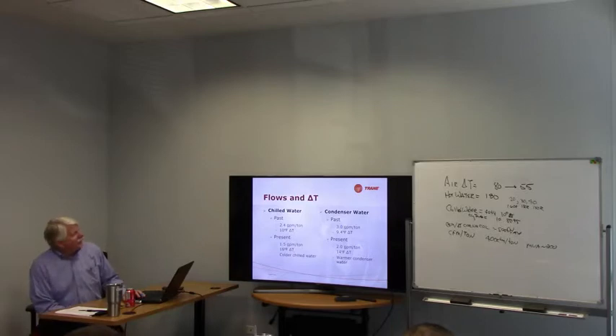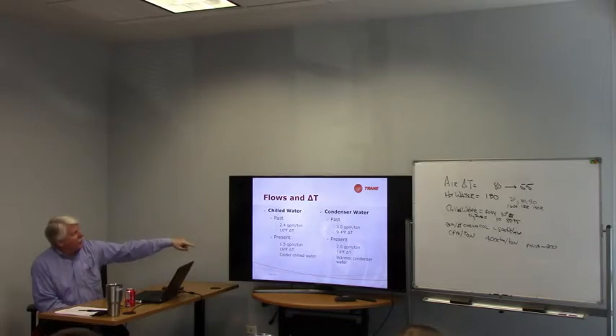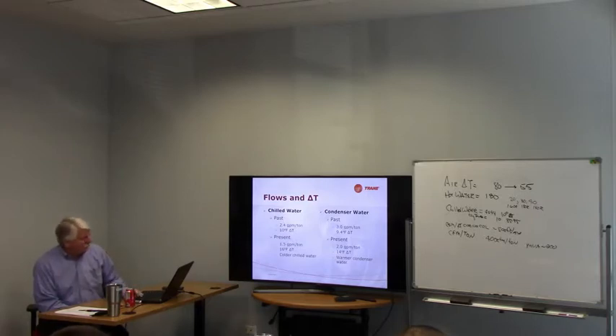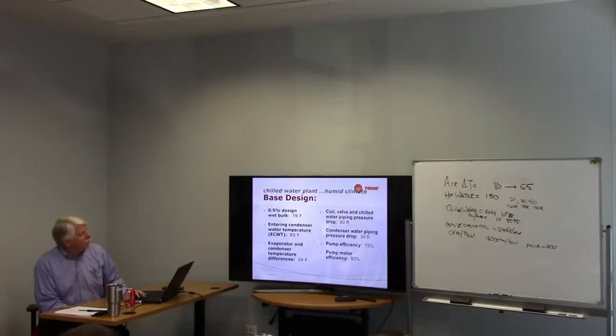So in the past, the chilled water was 2.4 GPM per ton at a 10 degree delta T. And we're trying to move that to 1.5 GPM at 16. Condenser water used to be 3 GPM per ton at 9 or 10 degrees. And we're trying to get that to 2 GPM. And those flows will result in a more efficient system than what we're doing now.